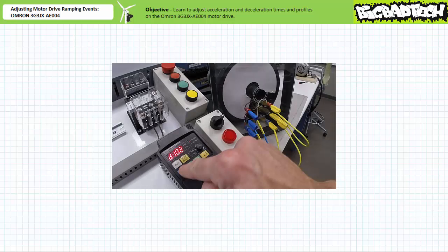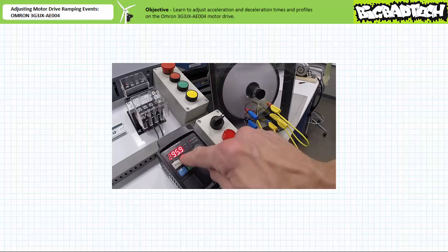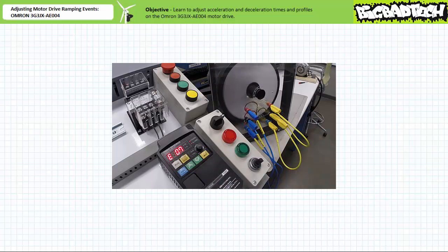As further evidence of what's going on during this overvoltage event during deceleration, let's monitor the DC link value during the deceleration process. Navigate to monitor function D102, DC voltage monitor, and press Mode to display the value. At rest, the DC link is just shy of 300 volts. When accelerating, the DC link briefly dips and stabilizes when the motor reaches full speed. During deceleration, the DC link spikes and errors out at greater than 380-ish volts.